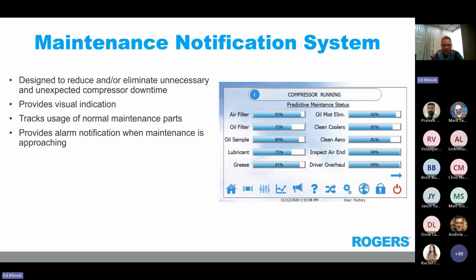Maintenance notification system. I mentioned earlier that FS-Elliott offers remote monitoring, as do a lot of OEM equipment manufacturers. The maintenance notification system works like some of the newer technology with cars, where it tells you when you need an oil change. It tracks the usage of normal maintenance parts and advises you when maintenance is approaching. These types of notifications are provided as visual indications on the HMI. They have alarm notifications, and a lot of DCS customers look at these through their Modbus protocol. The overall goal of this feature is to ensure maximum compressor uptime. So in today's technology, the maintenance notification system is big.